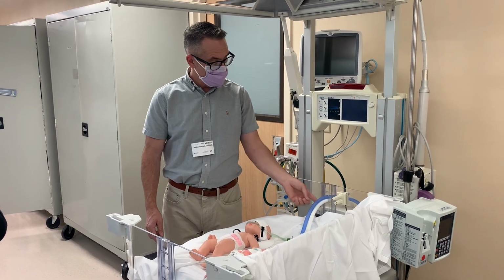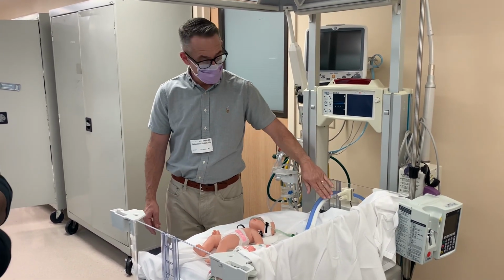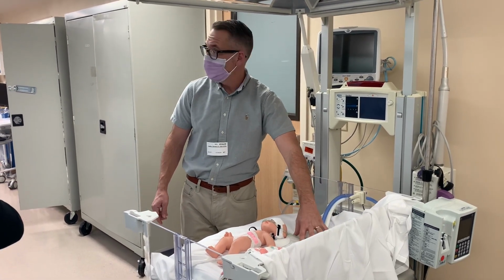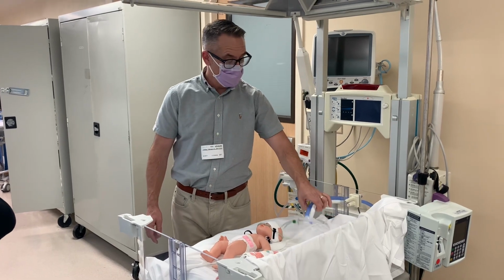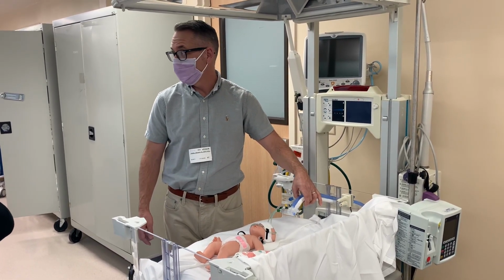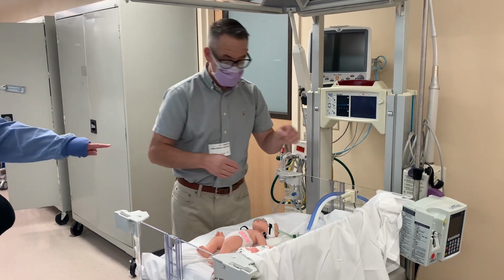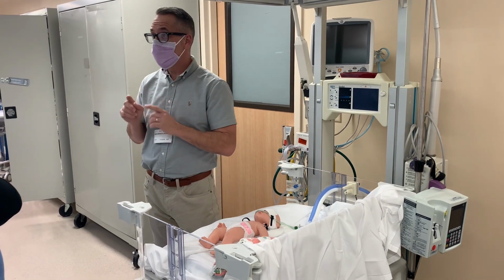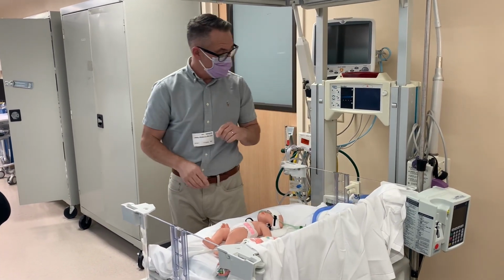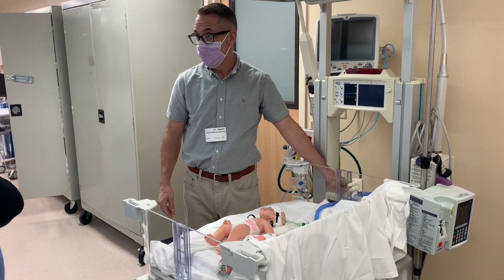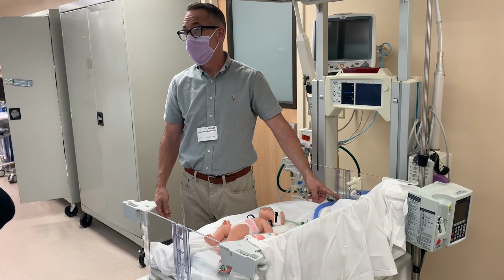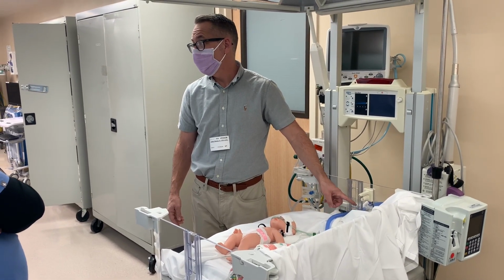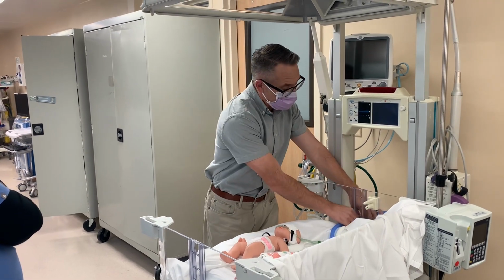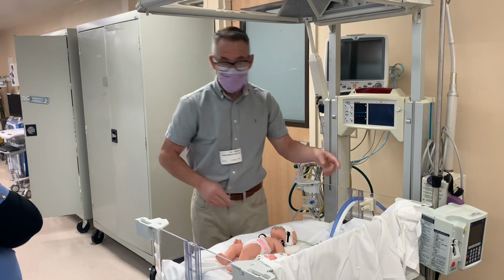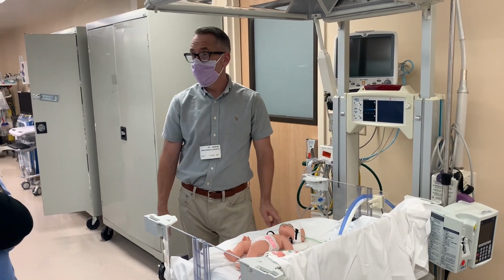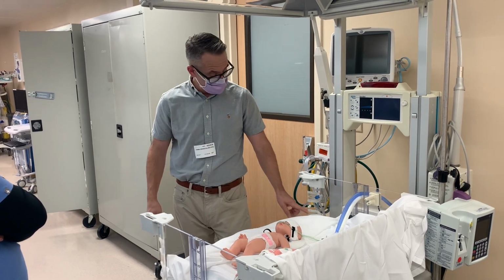And whenever you run this through the center opening, you almost invariably know you're creating this apex, so the water just continually flows down this direction and starts to fill up this area with water. If you use a circuit holder as well, that only compounds the issue, because now you have multiple apexes and all kinds of things that are collecting. So even if you position it all the way down the bottom of that opening? If you position it down the bottom, this is definitely more ideal. Sometimes the circuits then are laying over this plastic part, you keep another apex. The problem with this one is that means you'd have to get 100% of the RTs and nurses doing that 100% of the time. And it's too much of a variable where we go into hospitals and they just find a way. Over time, the circuit starts to rise. When you put it in a side corner hole, it's a finite thing. There's nothing you can do about it. When you put it there, that's where it goes.